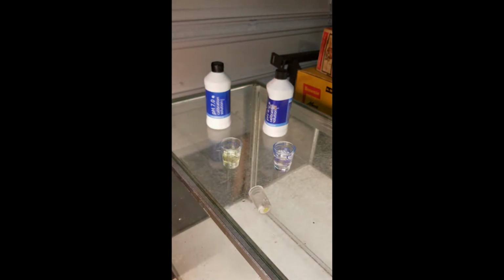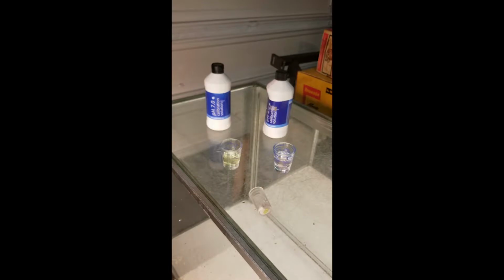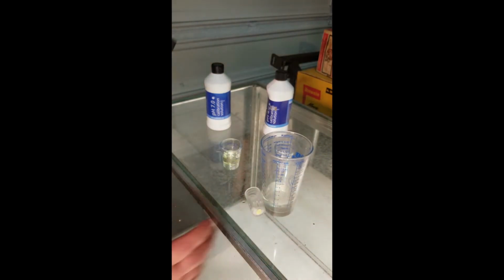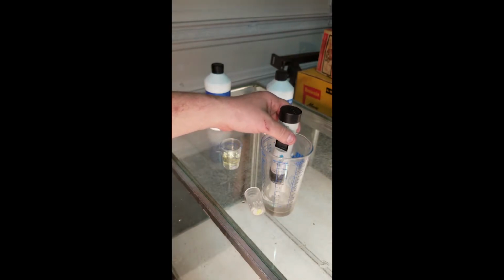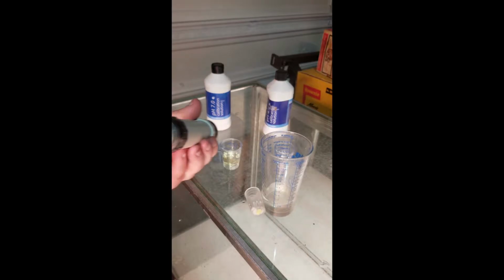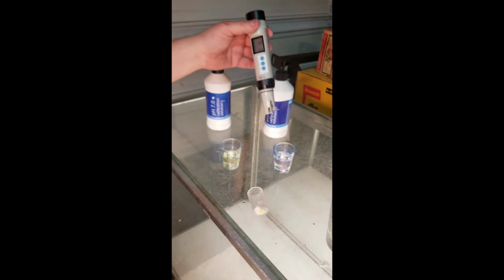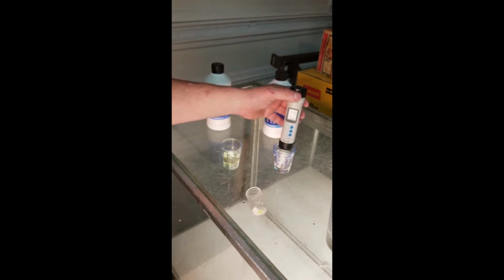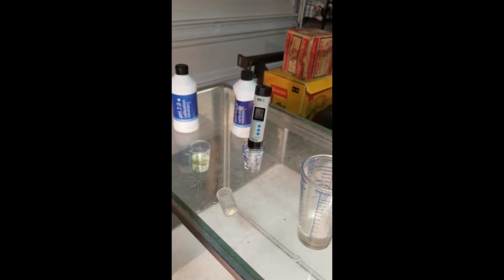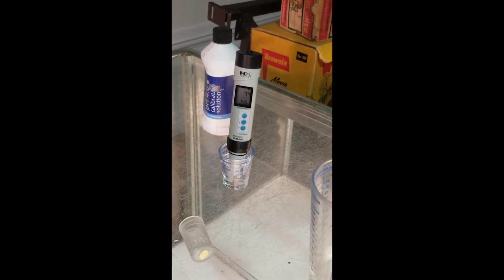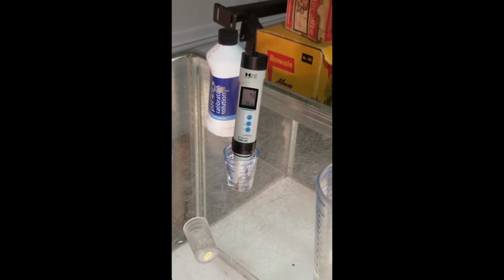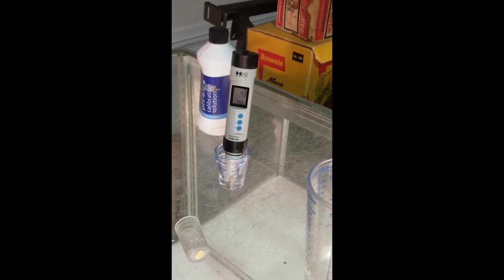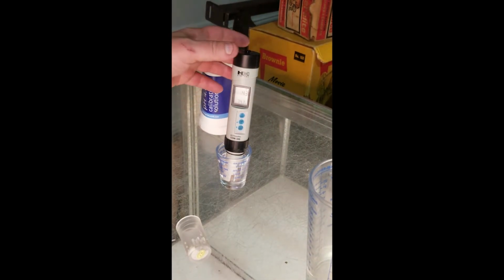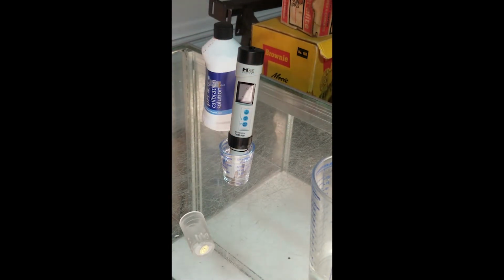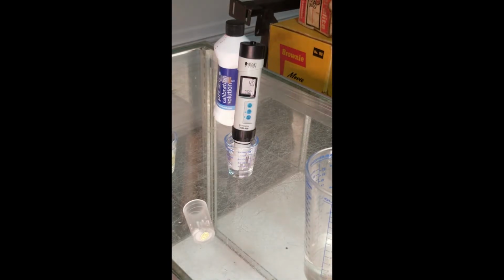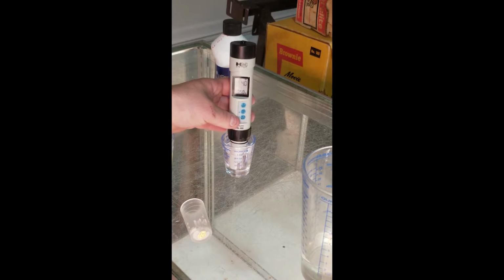I'm going to take a little bit of clean water just to get that neutral 7 off the tip and basically cleaned, so I can get the most accurate reading when I go to the 4. So now I'll go in the pH of 4, and we can see that it's dropping down. Now this should be more accurate than it was before, but it's now correct. So we'll give that just a few seconds to finish up. And it looks like this one actually, just from calibrating the top end to 7, this one went to 4. So I'm not going to change this.